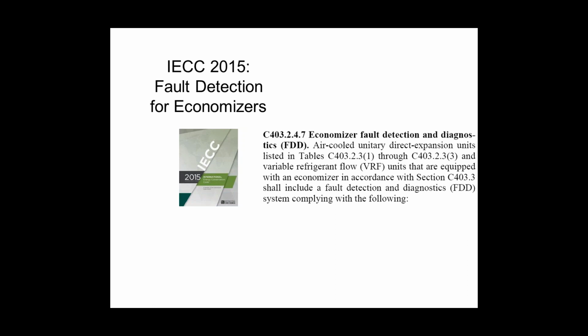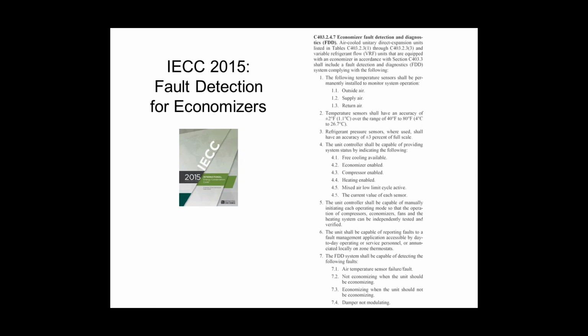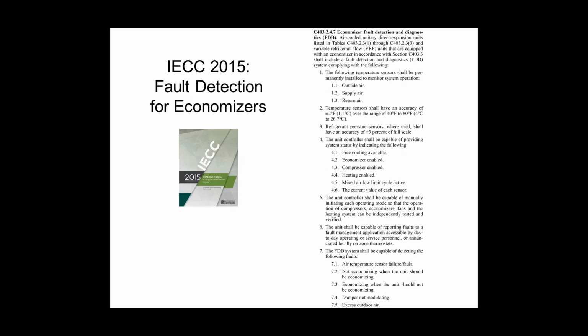The really big change on economizers, and then we'll get off economizers, I promise, it's just there's been so much stuff on the economizer side, is that there's a new section that requires the economizer to have fault detection and diagnostics. And it has its own acronym, FDD, and you know if it has an acronym, it's the real deal, right? It's a real HVAC thing if we assign an acronym to it. It's a big, long section, it's huge. I'm not going to read through it to you. But basically, your economizer controller has to have the ability to detect all kinds of problems that it could have, such as a problem with the temperature sensor readings, the economizer not opening when it's supposed to be opening, the economizer not shutting when it's supposed to be shutting, damper blades getting stuck, too much outside air, things like that. So I've got to monitor this thing, and if I have a fault, I have to determine that fault. And specifically, let me get my John Madden pen back out, right?